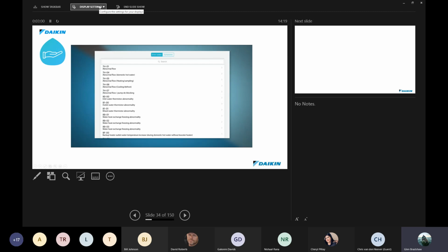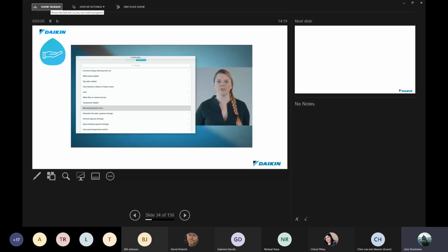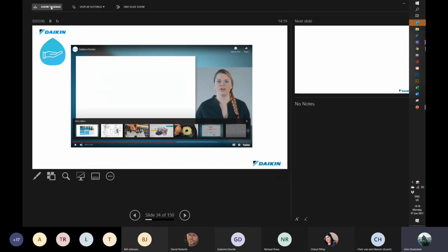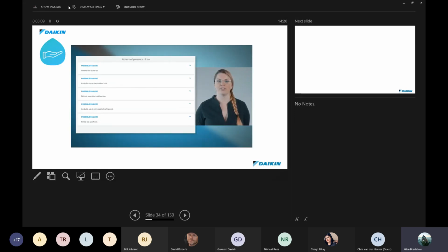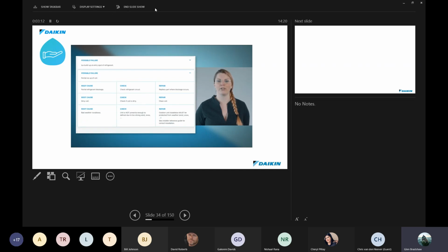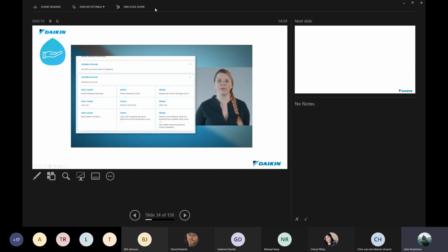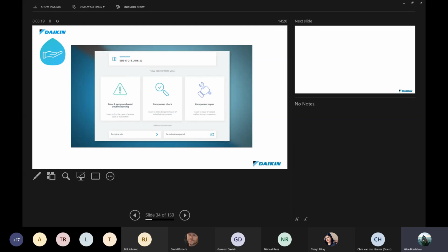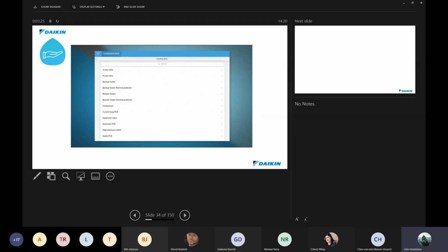Let's go back to our troubleshooting and focus on symptoms now. In the symptom-based troubleshooting, we'll find a list of all known symptoms. Each symptom can have more than one possible failure. A root cause, check, and repair instruction is given for each failure. When we go back to the home screen of EDoctor, the second possibility is to start your troubleshooting with the component check.